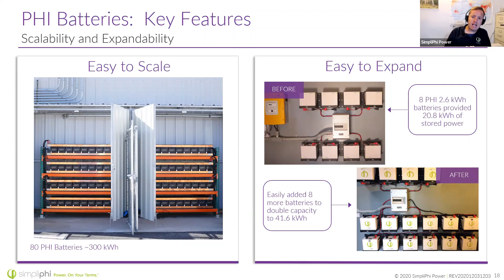When it comes to maintaining batteries, it's a real advantage to have sealed batteries. A sealed battery isn't going to vent or release gas over time, so you don't have to come back and water it. When you're making that sale to the homeowner and you hear, 'don't worry about maintenance plans, I can water my own batteries, I can take care of them,' inevitably you come back a year or two later to troubleshoot and discover the homeowner didn't water their batteries, and the whole system is dead.